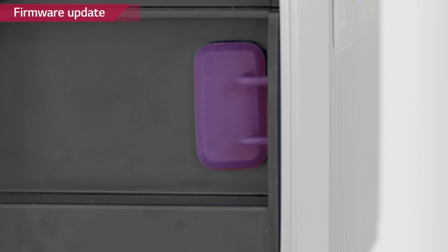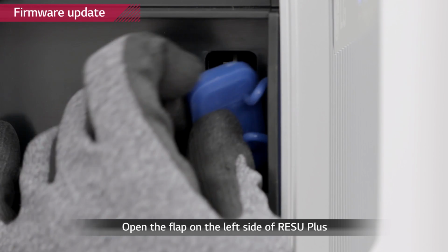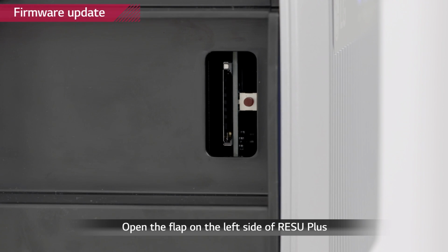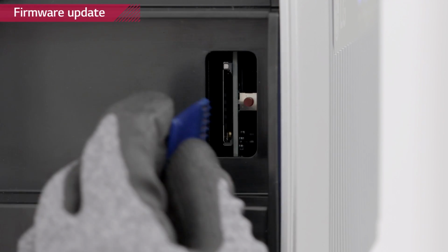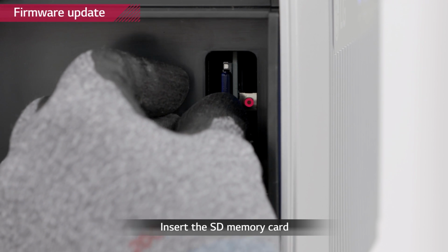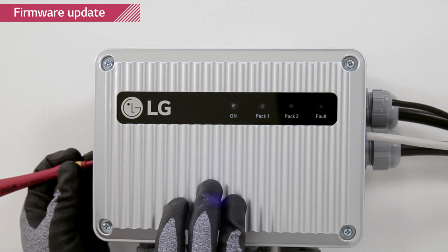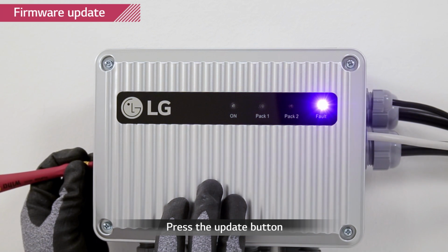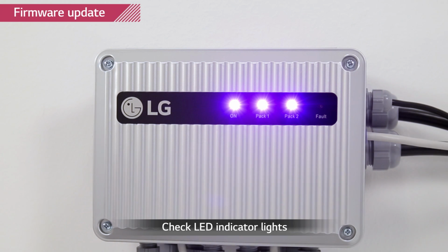For firmware update of RESU Plus, LG Chem recommends to use one of the SD cards stated in the installation manual. Open the blue rubber cover on the left side of the RESU Plus. Insert the SD card and press the red button for 3 seconds. The lights will begin to flash from left to right. When the update is finished properly, the 3 lights will be lit at the end.